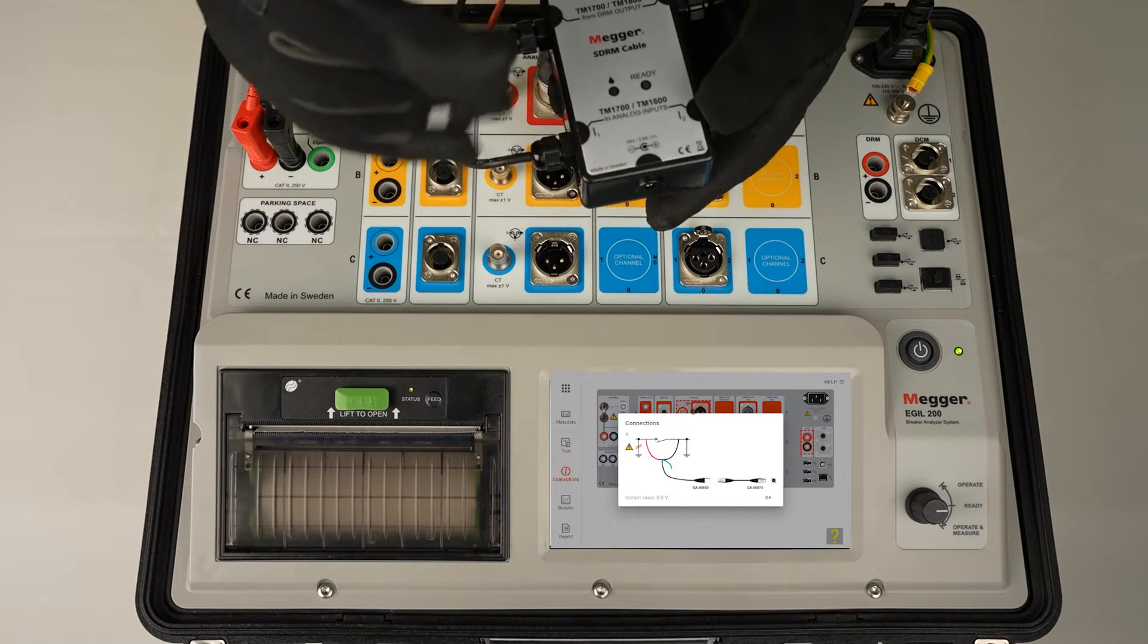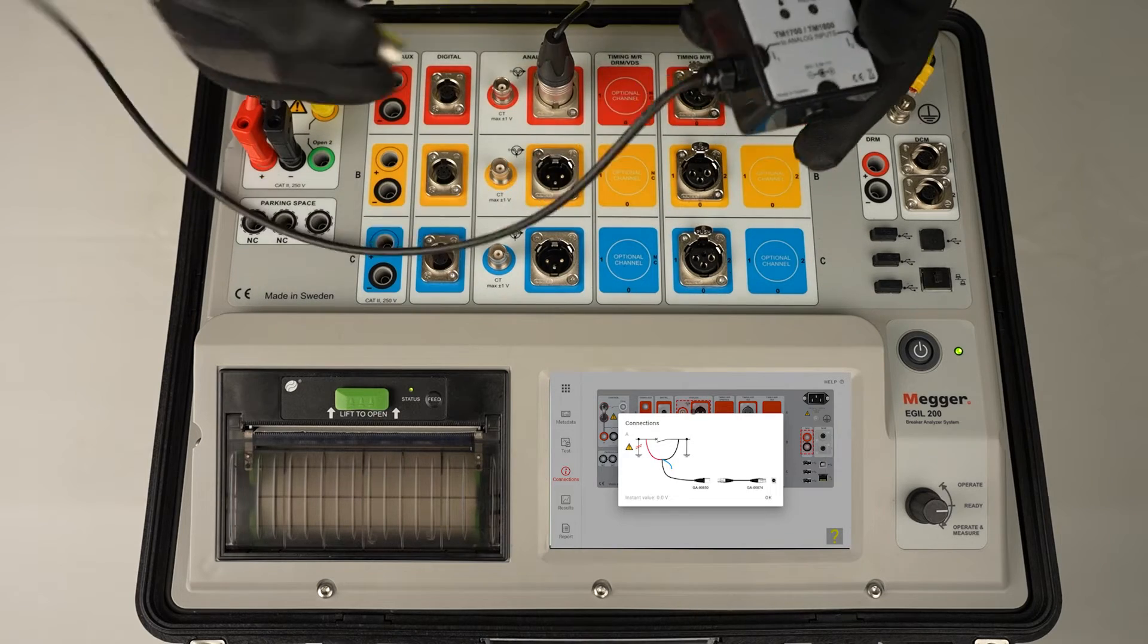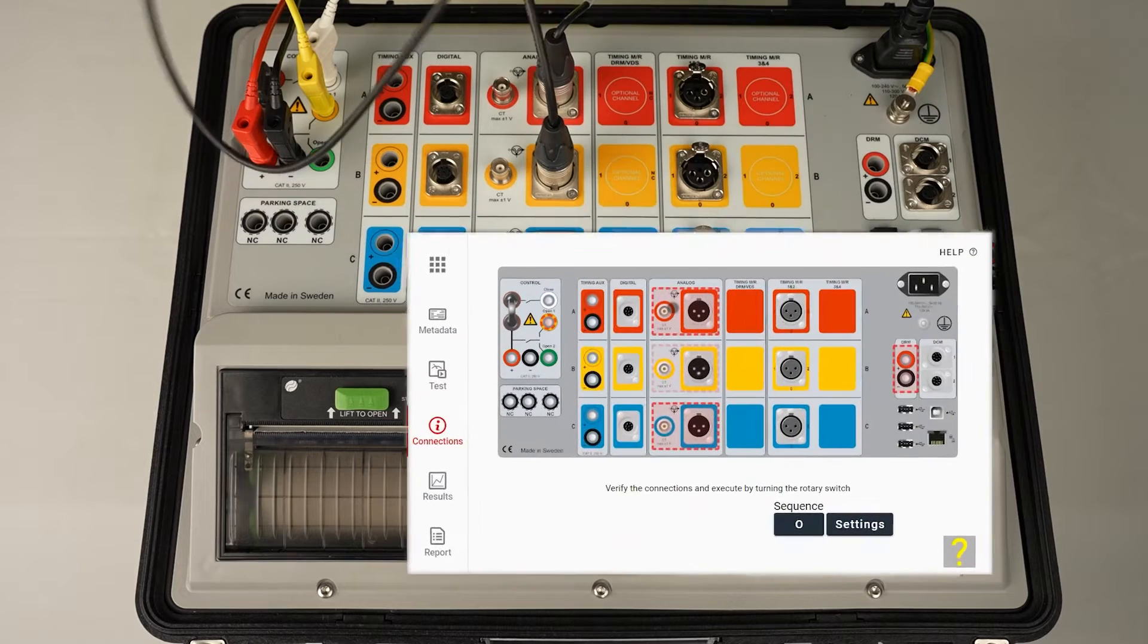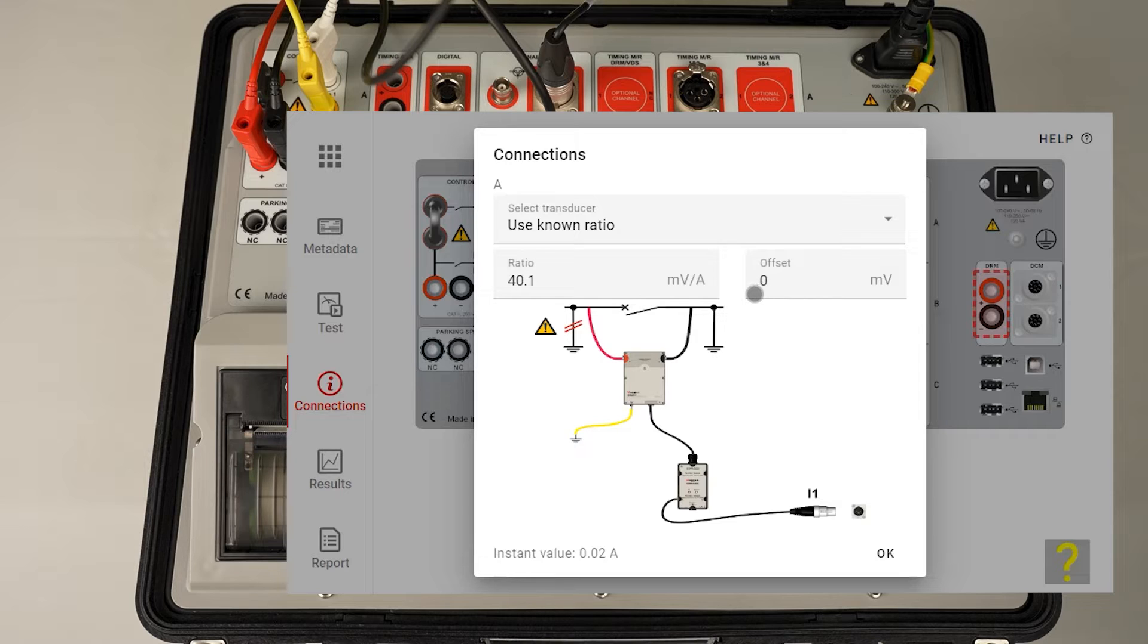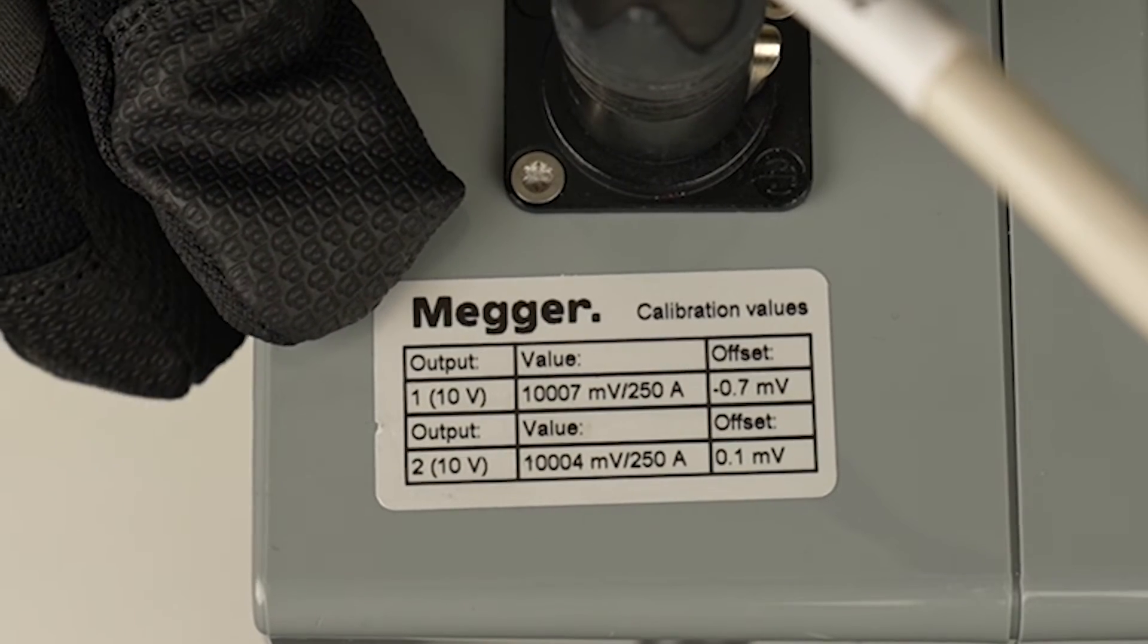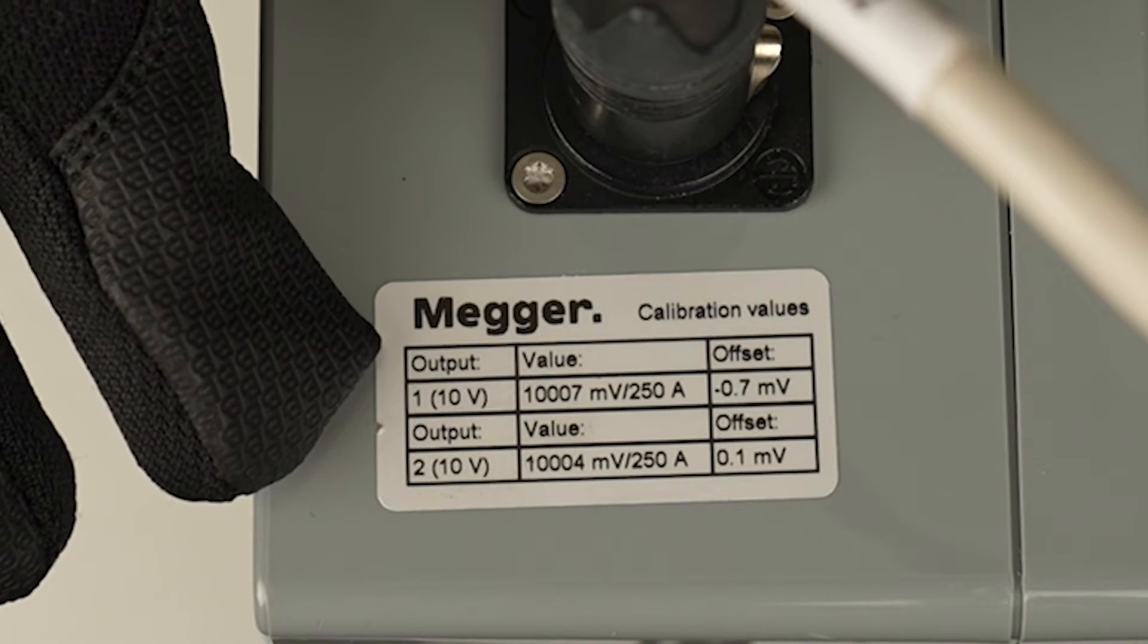We use the SDRM cable and connect the channel 1 to analog channel. Here I need to fill in the ratio. The ratio you can find on the label on the SDRM box. My specific value is 10007 and I need to divide that with 250.